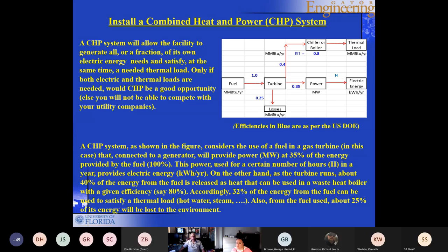It's going to provide electric energy in kilowatt hour per year. And at the same time, the turbine is going to run at about 40%. Of the energy from the fuel, 40% is going to be lost as heat, which can be recovered in a waste heat boiler. And we assume that the waste heat boiler has an efficiency of 80%. And therefore, you will end up with about 32% of the energy from the fuel can, in fact, be used to satisfy the thermal load.